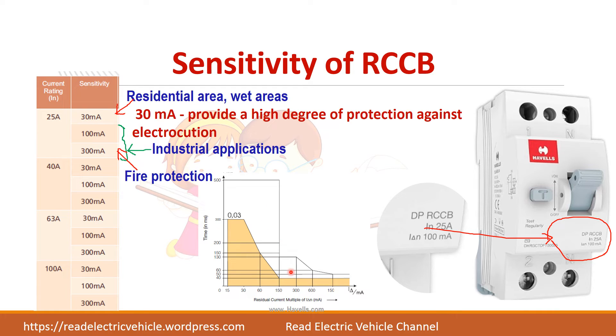This chart shows the residual current and the time period at which the breaker will trip. When it is 30 milliamps, it takes 300 milliseconds to trip. As the current increases, the tripping time should be lower for the safety of human beings.